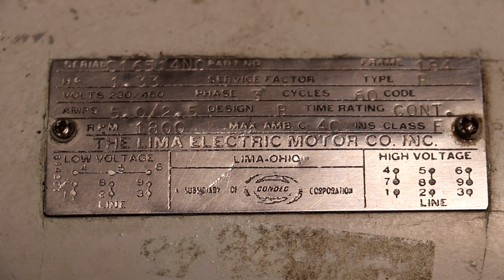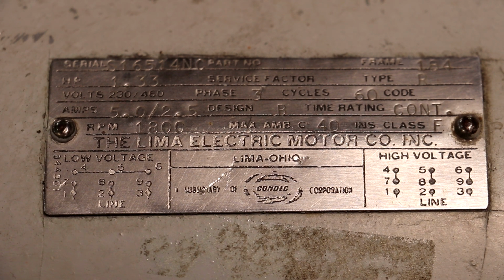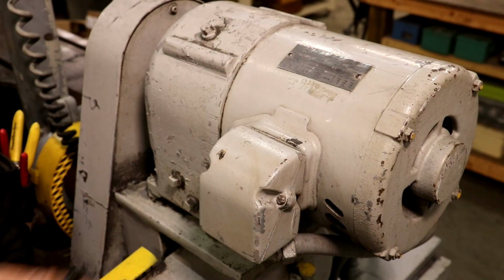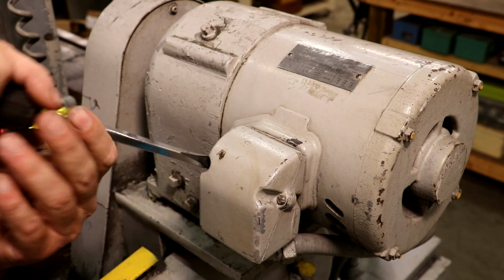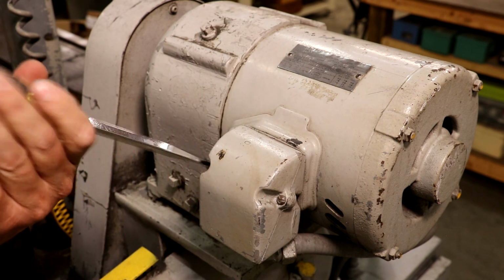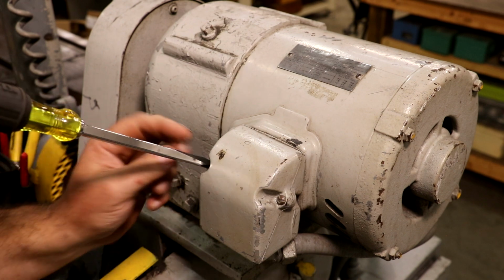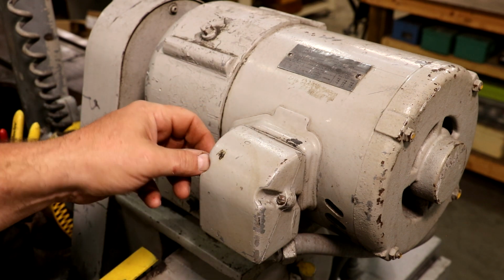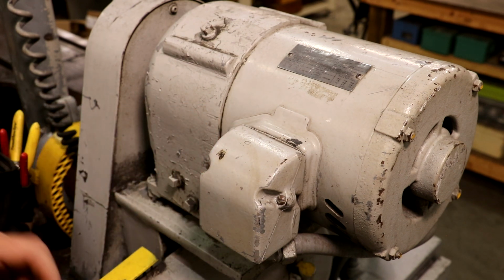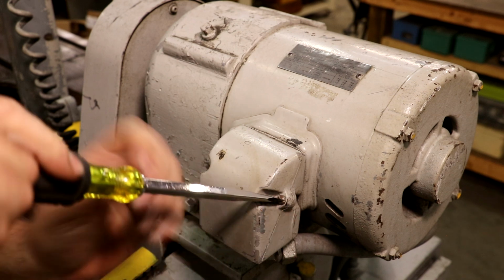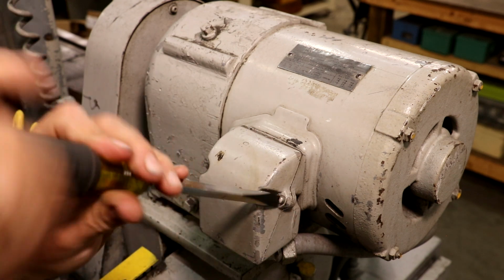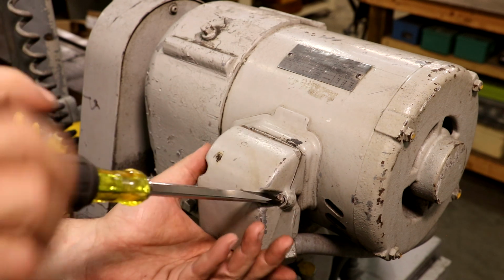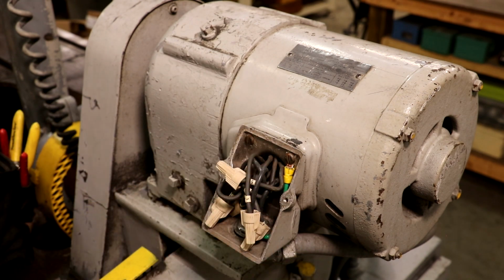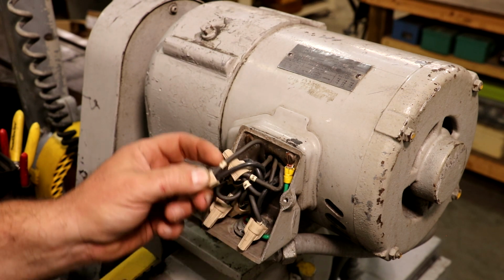So let's pull that pecker head apart and go ahead and take a look at that. So we'll take a screwdriver here and we're going to open up this pecker head. This is basically where all the wires come out of the motor and where you connect the wires that go to your motor starter. And we'll see what we got. All right, so it looks good. The wires are marked. You see they all got the numbers on them.